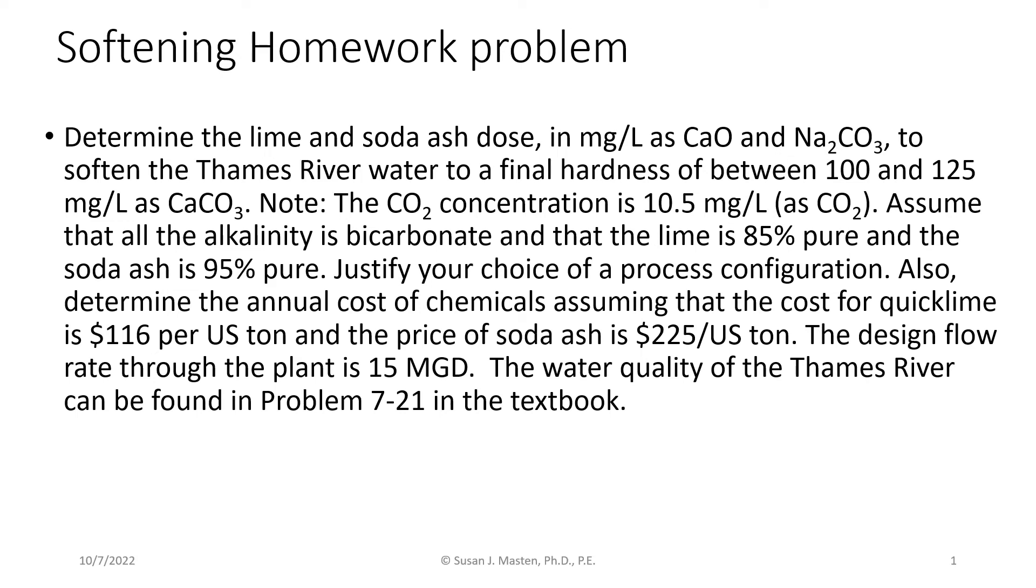In this homework problem, you're asked to determine the lime and soda ash dose in milligrams as calcium oxide, because that's what we add, and sodium carbonate, or soda ash, to soften the Thames River water to a final hardness between 100 and 125 milligrams per liter as calcium carbonate.